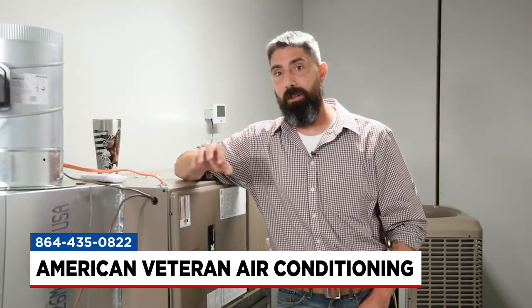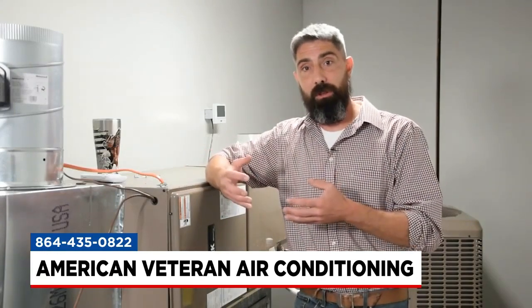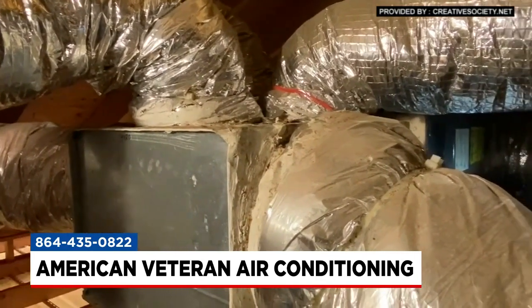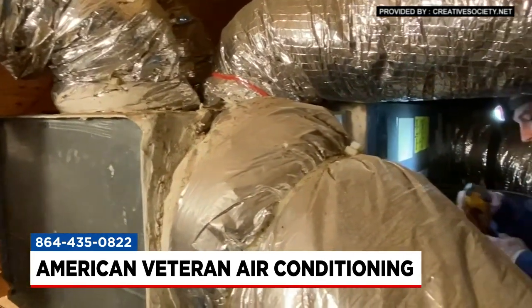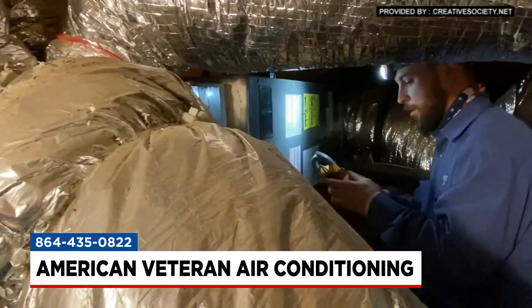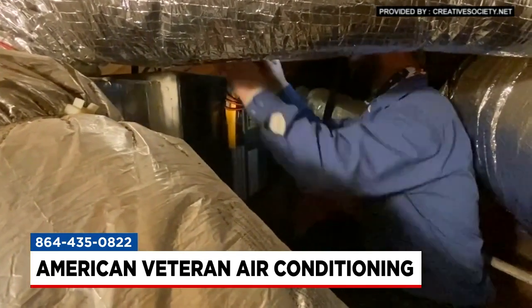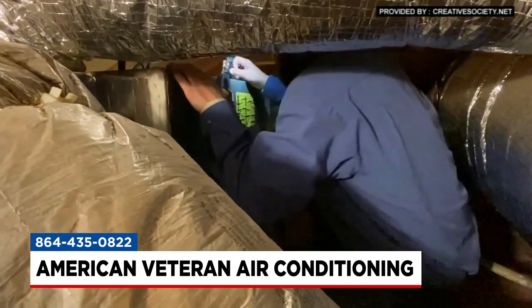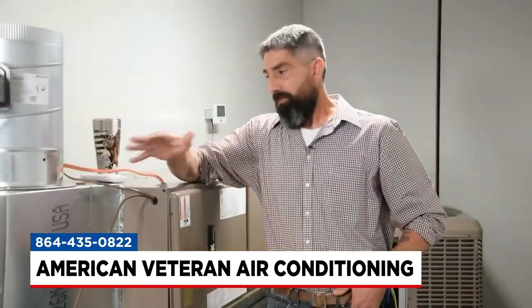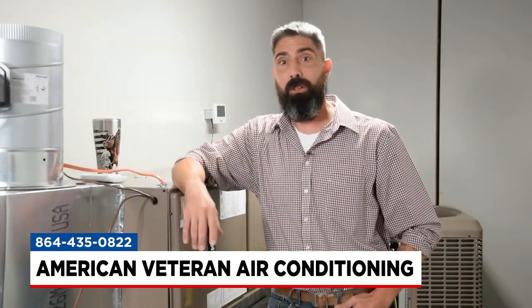It's very common. A lot of times when we go to a house and they think they need a larger machine, but really what they need is to tighten up their duct work to allow all that air to get through. You go to energy.gov and they're going to tell you that the majority of folks have about 30% of the air they're trying to get into their house leaking out of their duct work before it gets in there. Those are probably somewhat overestimated numbers, but it's a decent baseline, and we have seen where that is pretty close to the truth in a lot of cases.